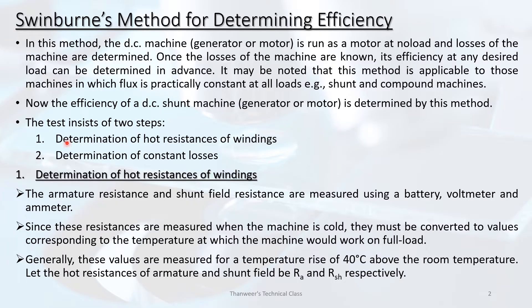The test involves two parts: determination of hot resistances of windings, and determination of constant losses. For the first part, the armature resistance and shunt field resistance are measured using a battery, voltmeter, and ammeter.